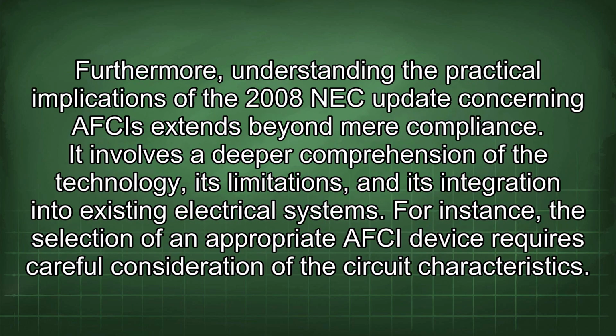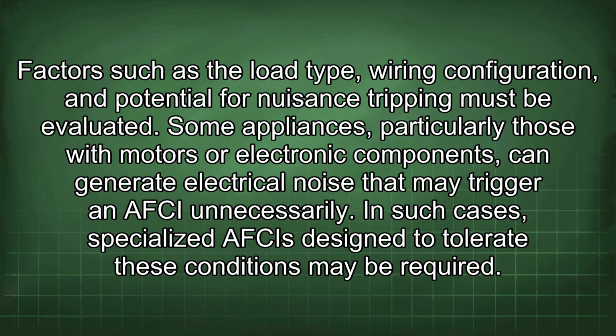Furthermore, understanding the practical implications of the 2008 NEC update concerning AFCIs extends beyond mere compliance. It involves a deeper comprehension of the technology, its limitations, and its integration into existing electrical systems. For instance, the selection of an appropriate AFCI device requires careful consideration of the circuit characteristics. Factors such as the load type, wiring configuration, and potential for nuisance tripping must be evaluated.